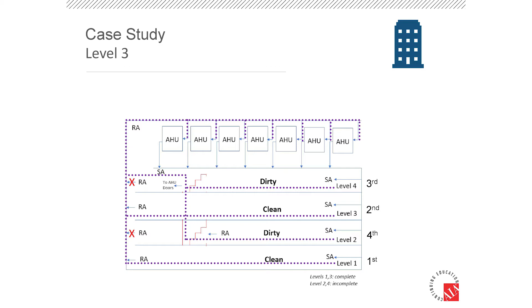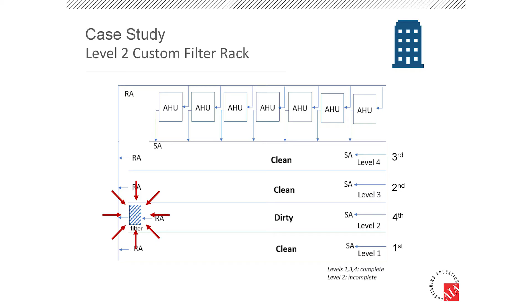The only hiccup to that plan was the owner mentioned, oh by the way, level 2 isn't going to be remotely clean, we're still designing it, it's going to be lagging 6 months down the road. So in order to get air to that floor without it being oddly pressurized, they asked the engineer of record, hey, can you design a special return air plenum filter adapter for level 2's particular plenum, so we can open up that floor's return but have it all filtered there, and we'll just kind of monitor it. So that was what they ended up doing.